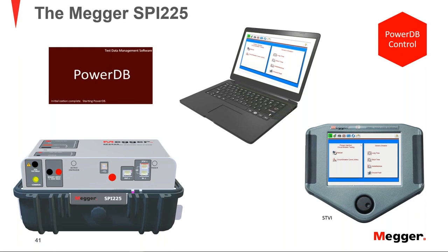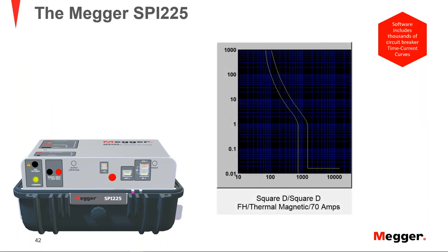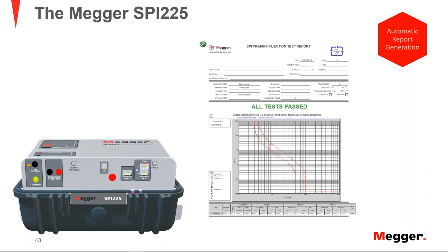The SPI is controlled using PowerDB software, either with a computer or a dedicated touch view interface — the software looks and behaves the same on both. The dedicated virtual form for the SPI includes thousands of time current curves for circuit breakers, so the software automatically plots your result against the curve and tells you if it's a pass or fail. If the circuit breaker isn't in the library, you can send a PDF and Megger will digitize it. Reports are automatically generated and ready to save as PDF or print in just a couple of clicks.